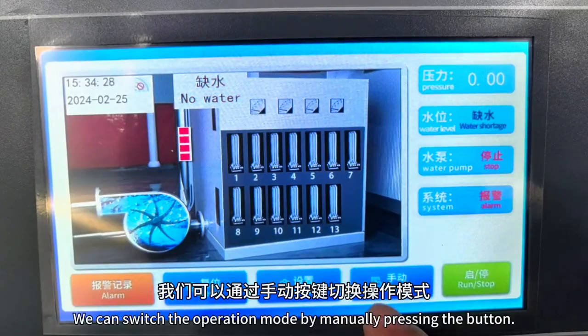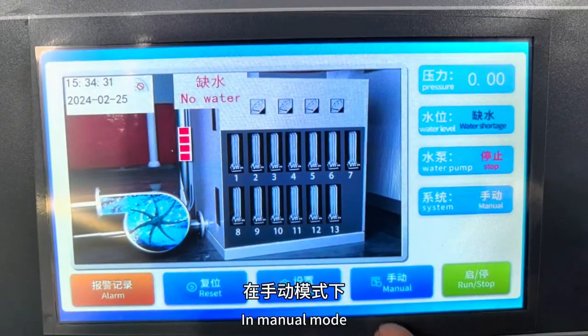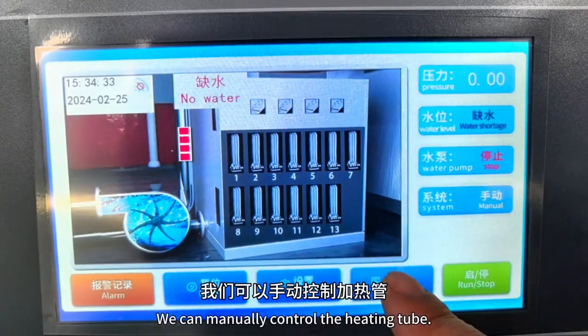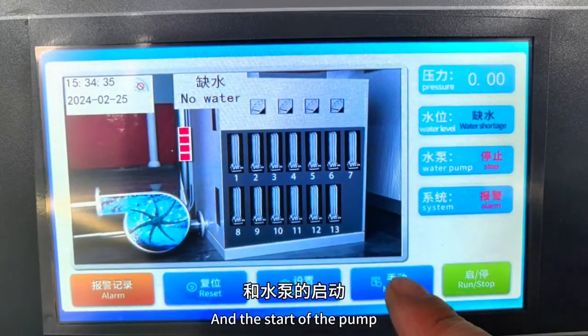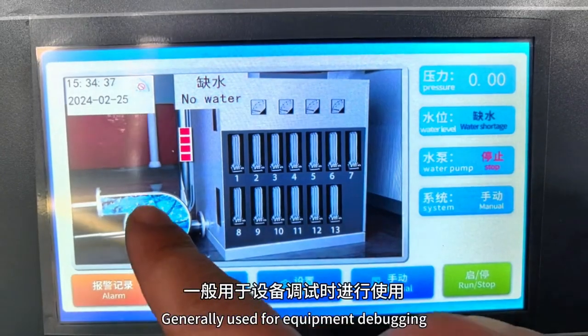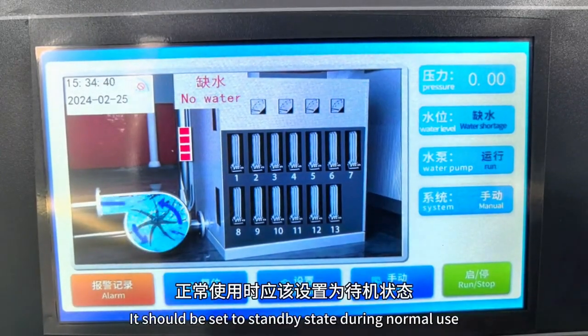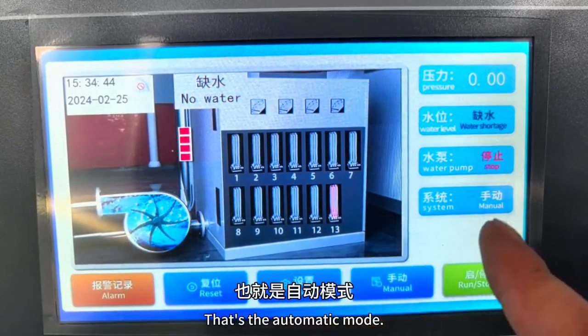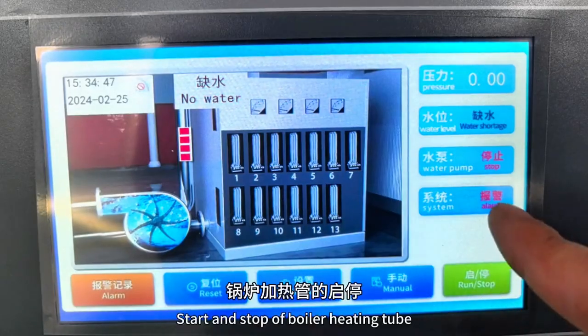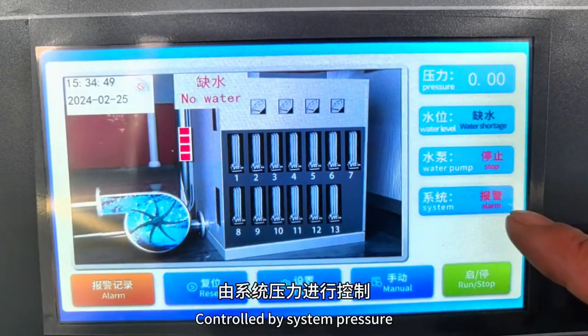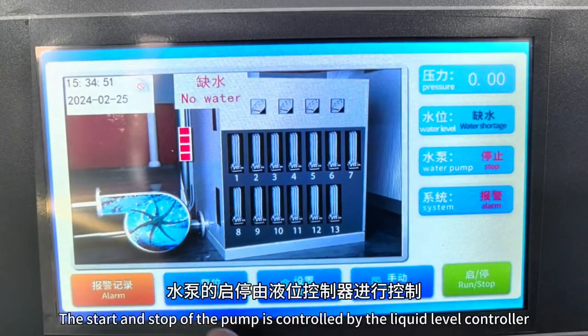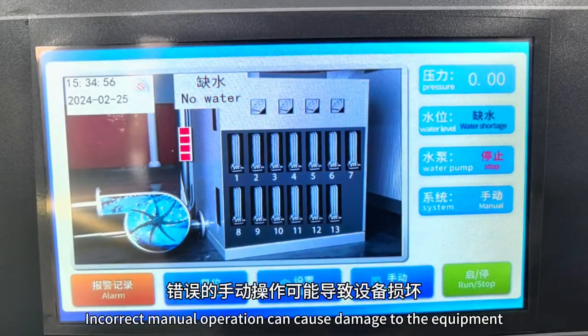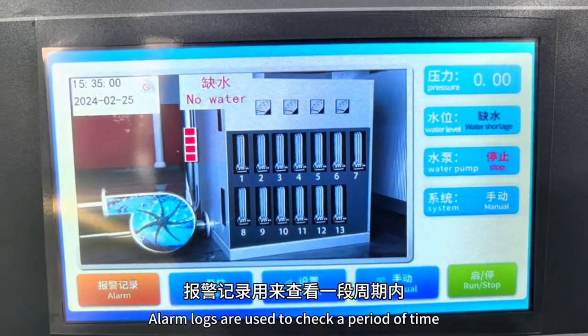The operation of the boiler is divided into two modes, manual and automatic. We can switch the operation mode through the manual button. In the manual mode, we can manually control the start of the heating tube and water pump, which is usually used during equipment debugging. When in normal use, it should be set to standby mode, which is automatic mode. In automatic mode, the start and stop of the boiler heating tube are controlled by the system pressure, and the start and stop of the water pump are controlled by the liquid level controller, without the need for manual operation. Incorrect manual operation may cause equipment damage.